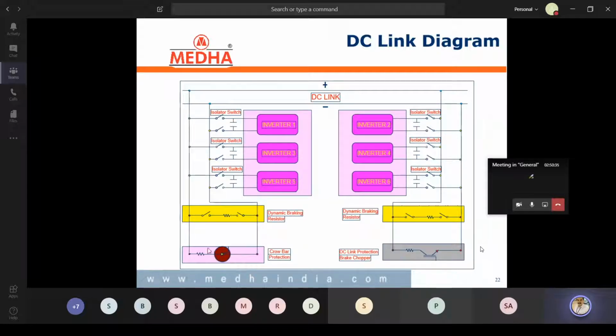Once it triggers, it will be in latch state, so excitation will be cut off. That is the difference, and based on practical experience and this field data, now in our locomotives we have eliminated the crowbar circuit. Only the brake chopper itself is controlling effectively. This is about the DC link circuits.